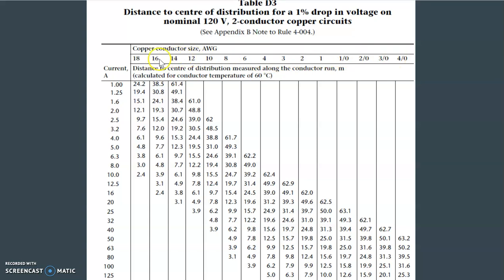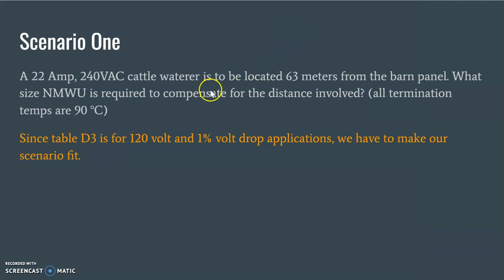And then we also have our AWG size across the top here, and those correspond to conductor sizes that we would see, starting at 14 AWG. They have an 18 and a 16 listed here as well. But those are your common wire sizes, and it just goes up to 4/0. Another thing to note about this particular table: 120 volts. So everything has to be 120 volts, and it only allows for a 1% voltage drop. So that's going to be a little bit tricky with the information that we have in our scenario. Because again, it's 240 volts, and you'll notice that our table in D3 is only for 120 volt and 1% volt drop applications. So we have to make our scenario fit.